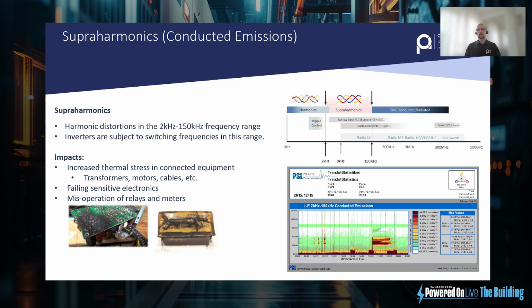Another thing to think about is understanding if you've got metering going on, we can produce things like a thermal heat map that you can see here on the bottom right hand corner. A thermal heat map allows us to understand which frequencies are present. And in addition to that, the effects of where maybe you've got some disturbances and you notice there's some problems on site, we can determine, oh, okay, it was between this time of day and we can see these frequencies were operating. Okay, solar inverters were on then. It could be that they were interfering with some other equipment. So very useful if you're measuring.